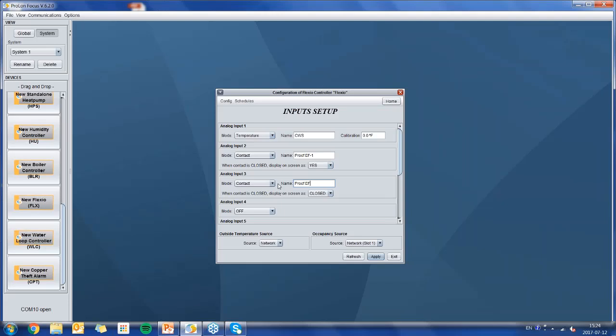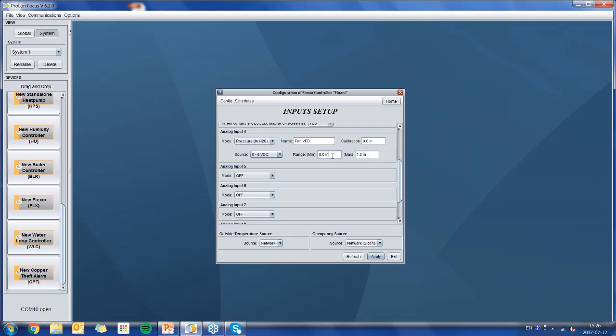I'll call it Fan VFD. Here we can choose whether it's a 0 to 5 volt, 1 to 5, 4 to 20, or 0.5 to 4.5 signal - it all depends on the pressure transducer. You can also set the range: 0 to 1 inches, 0 to 2 inches, 0 to half an inch - whichever transducer you have, the user can set up the range.